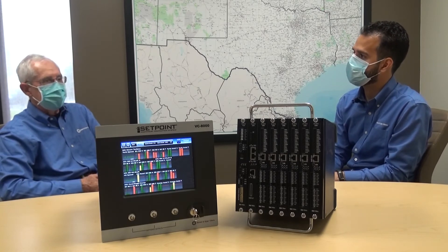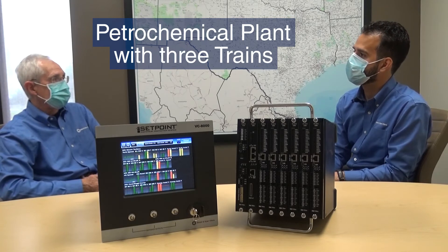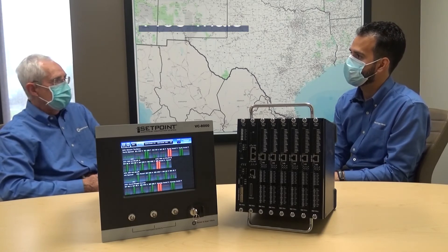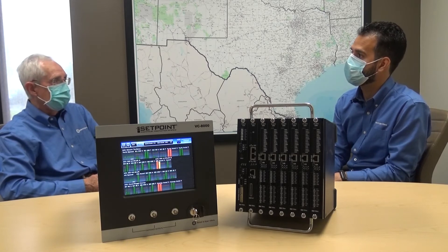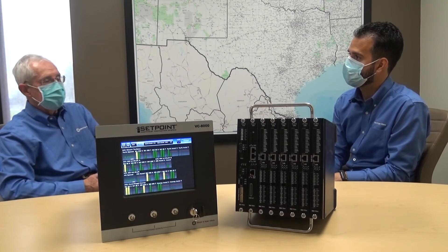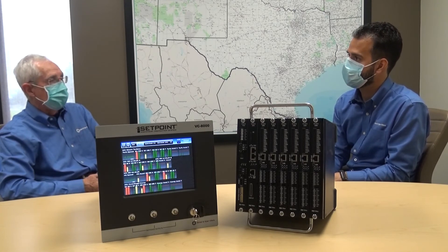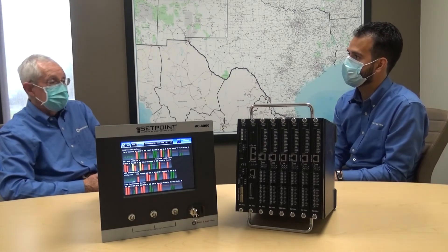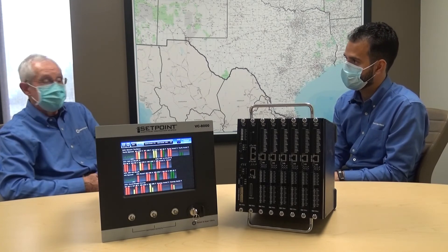This particular application was one in a petrochemical plant that had three main trains, such that if they lost one of the trains, they would have to have a complete outage. One of the things we're doing from a sales and marketing standpoint is offering free trials — we'll go in and actually put in a system for two to three weeks and let them evaluate the hardware as well as our condition monitoring software. We don't interrupt their operation at all; this can be done while they're operational. We simply take the buffered outputs from the existing system as input to our system. It simply digitizes the waveform that we're able to use with our condition monitoring software.